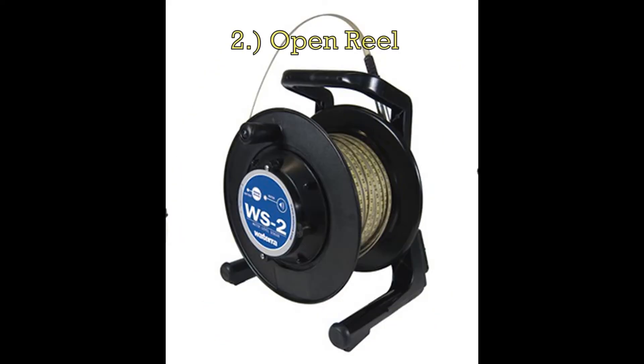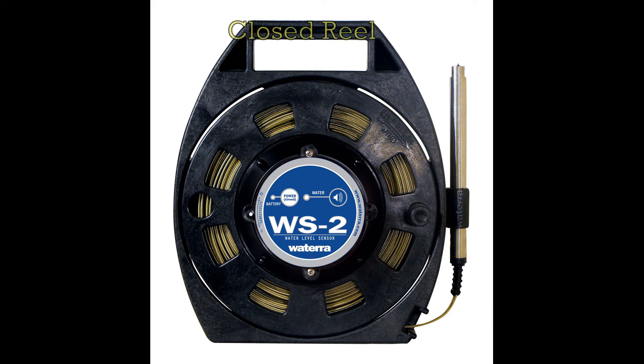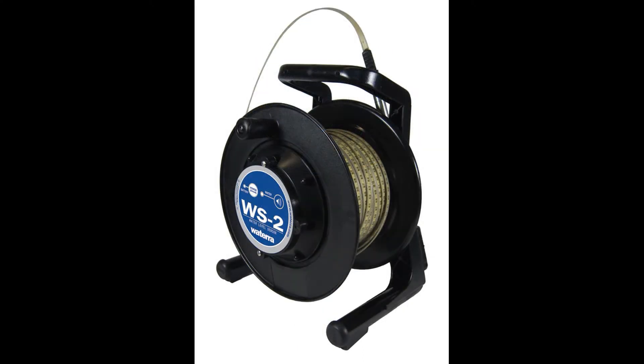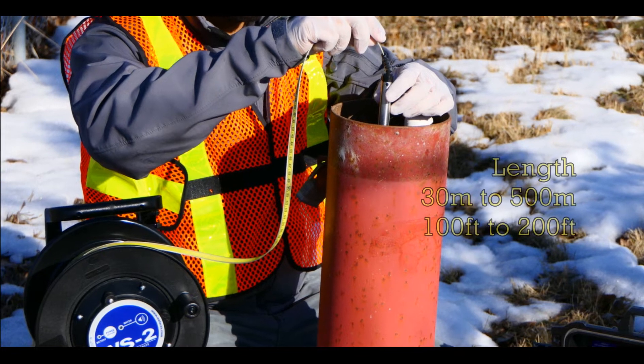This Waterra water level sensor comes in three different configurations: the closed reel, the open reel, and our newest product, the Reel Case. The closed reel is designed to protect the stainless steel tape from dirt and debris and is our lightest design, weighing about 7 pounds. The closed reel is limited to 30 meters or 100 feet of tape, whereas the open reel allows for much longer tape ranging from 30 meters all the way up to 500 meters in length.